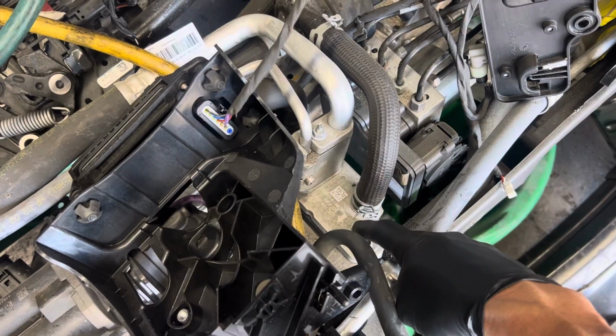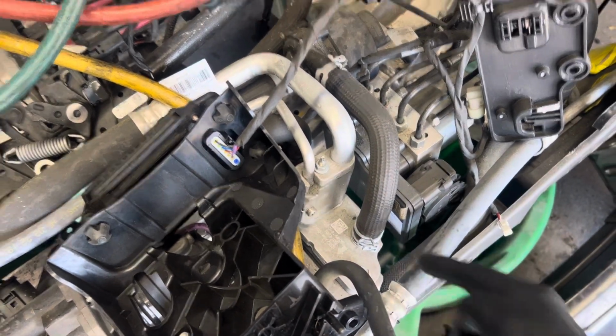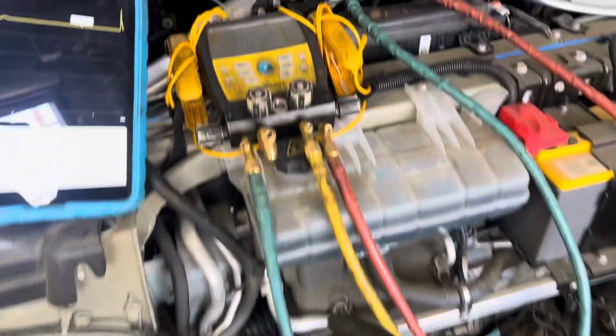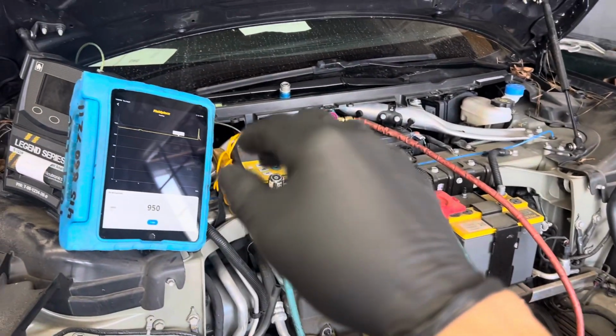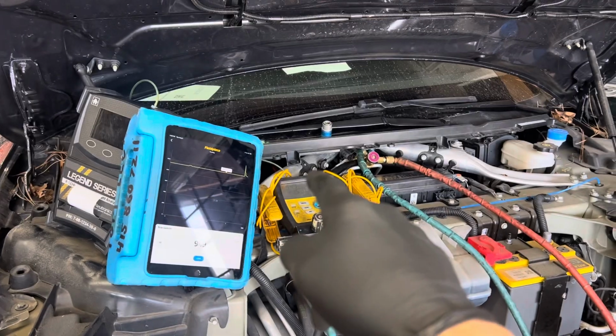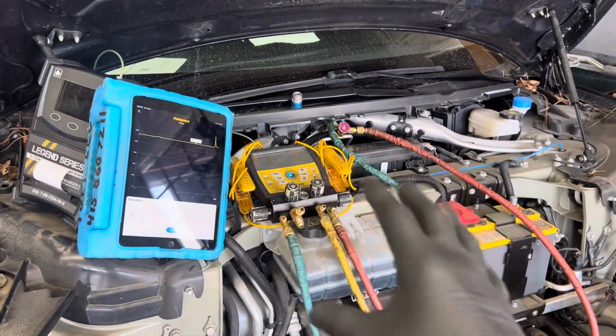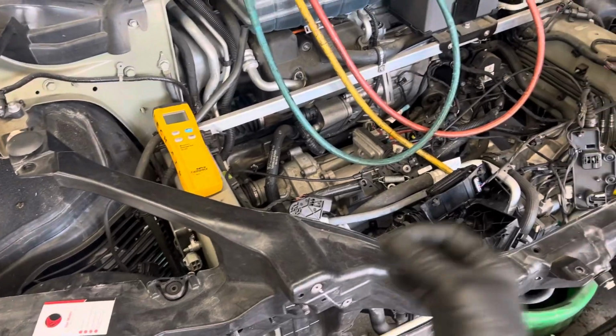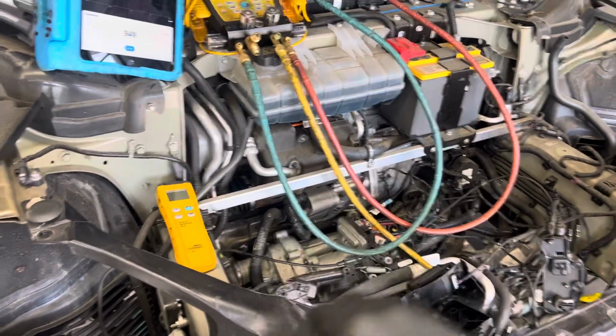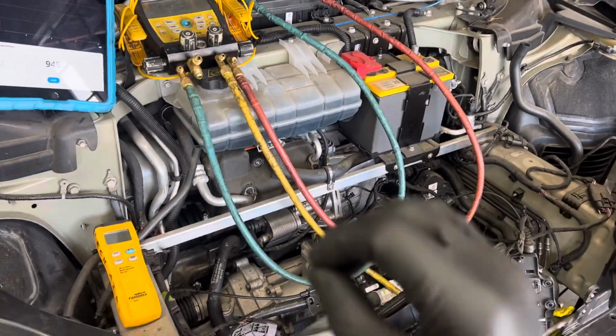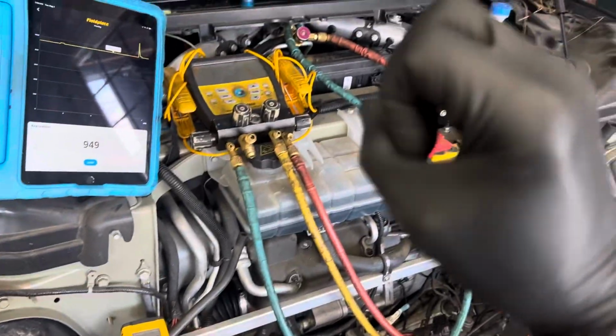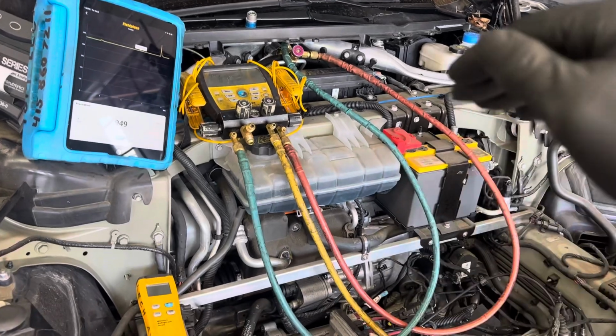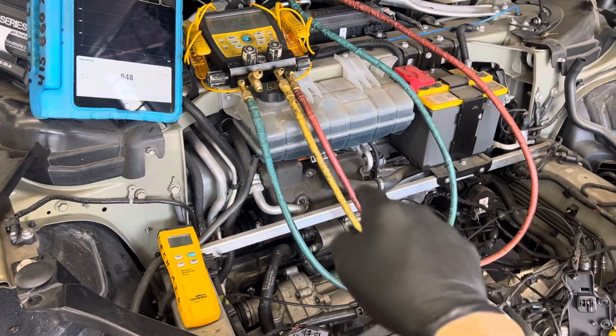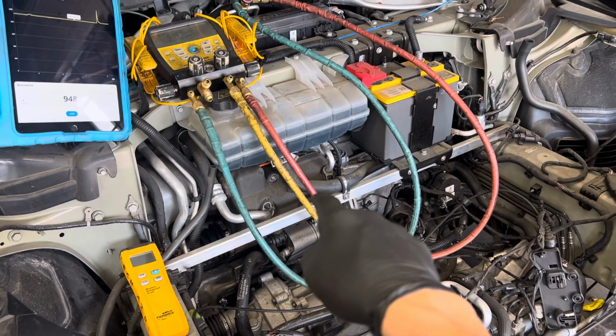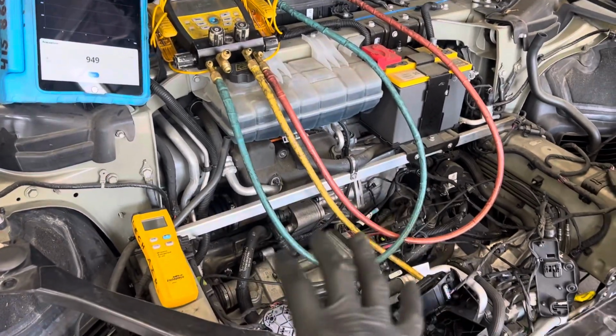where the liquid refrigerant gathers, like inside this plate heat exchanger, if I had an infrared camera on it, you would see it's cold. Any of the plate heat exchangers inside the bottom of the evaporator, it got cold inside there and there's oil in there. So when you open up a line and you hear that sucking sound of air going in, the minute that air that is hot and humid strikes the cold metal on the inside, it instantly flashes into liquid water droplets, and that goes directly into the POE oil that is used in this high voltage electric heat pump and contaminates the entire system.